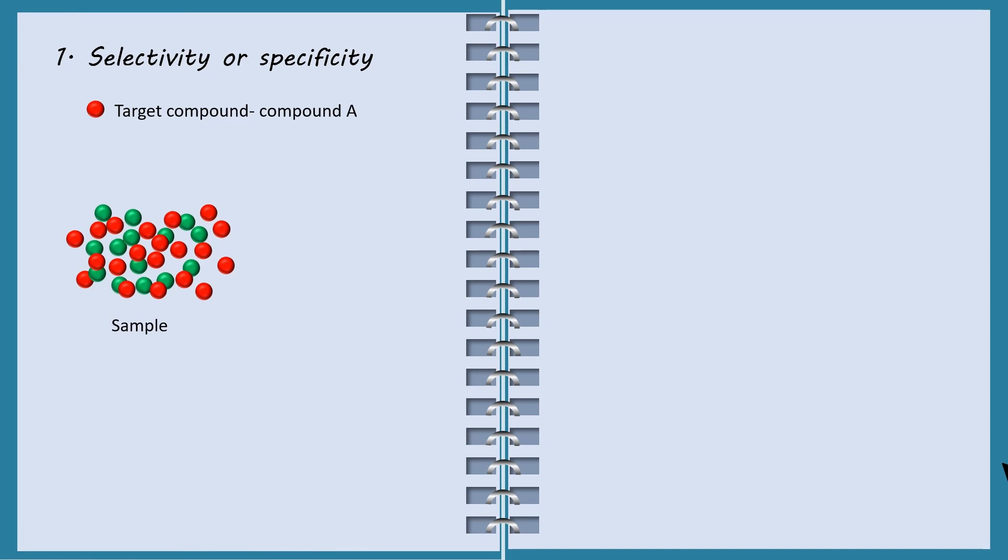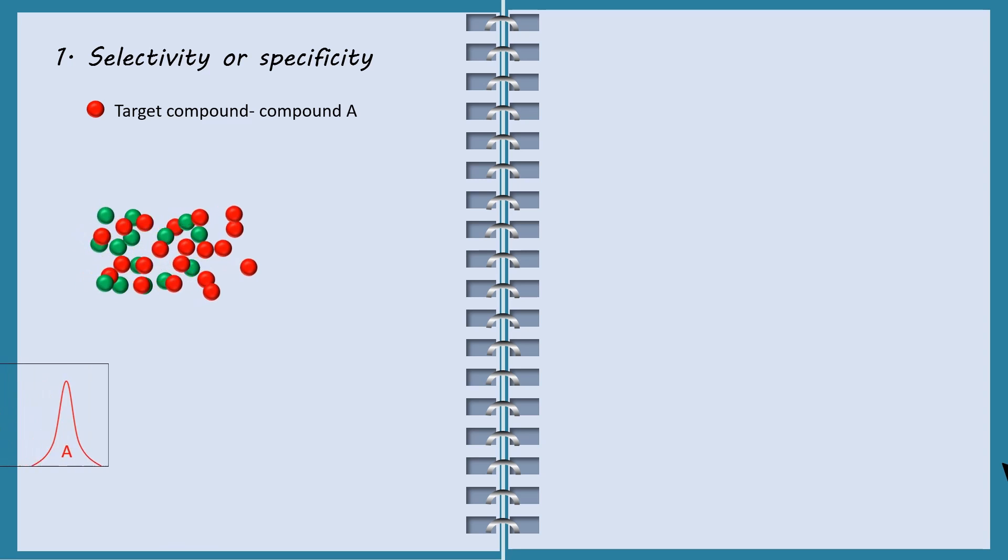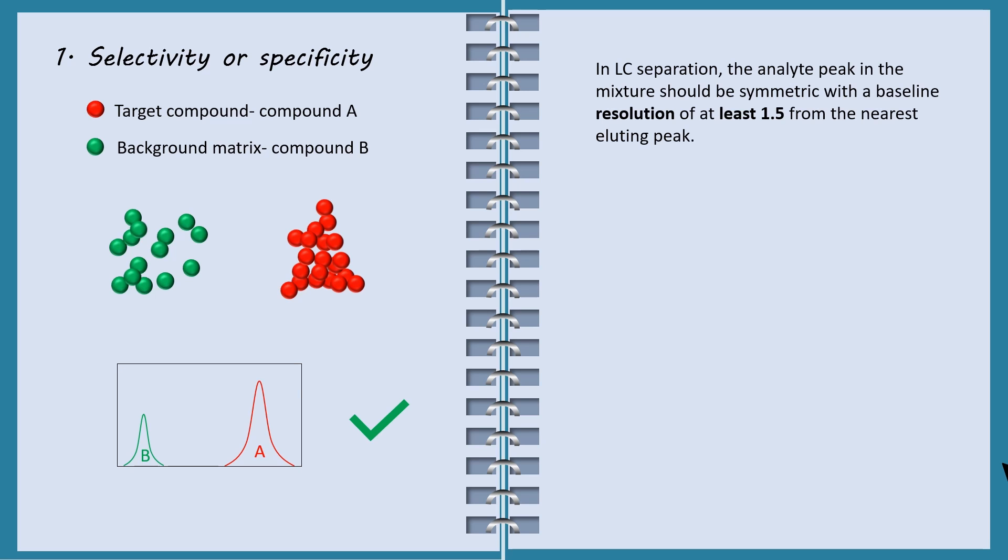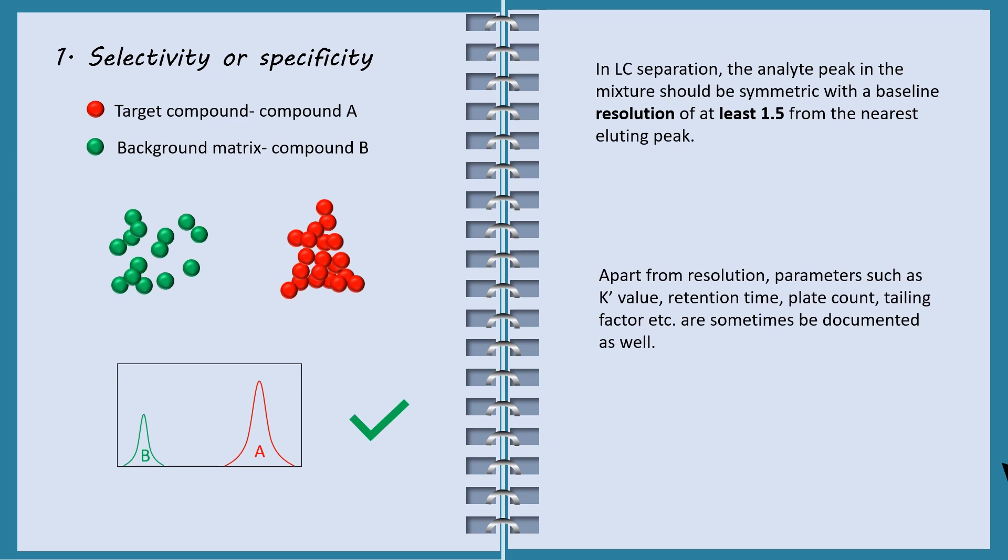Specificity is the ability to assess accurately the analyte of interest in the presence of components which may be expected to be present. In LC separation, the analyte peak in the mixture should be symmetric with a baseline resolution of at least 1.5 from the nearest eluting peak. LabSolutions software performs calculations to obtain these parameters. The values can then be printed and documented in validation report.